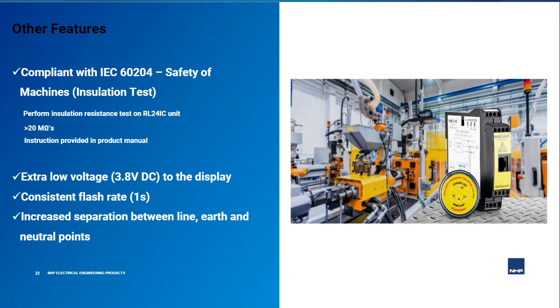We touched on this before when looking at the display unit. Worth highlighting again that this display unit has extra low voltage of 3.8 volts DC, which is safe for the user or operator in case they come into direct contact with it. The LED has a consistent flash rate of exactly 1 second. That's only the LEDs located on the sides of the REMLIVE display unit, for example the ones without the phase and the neutral marking. And there is convenient separation between the various connection points on the REMLIVE unit, for example the phase, earth, and neutral connection, to facilitate ease of wiring.